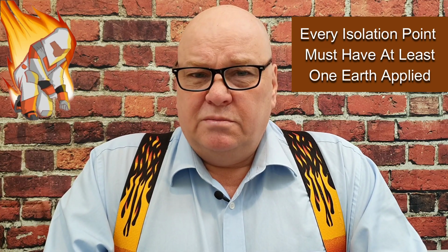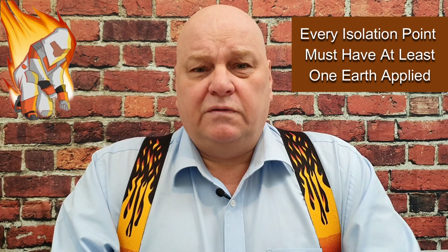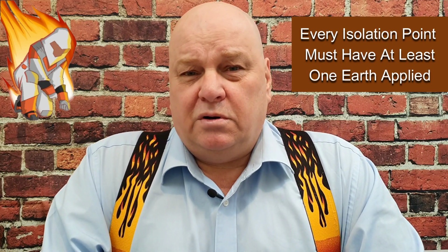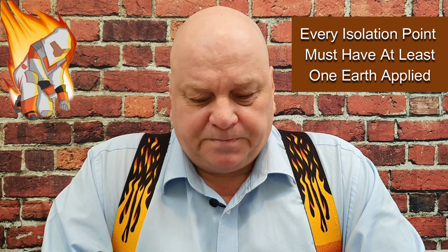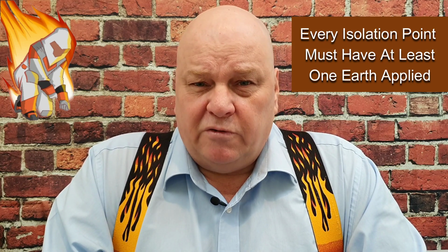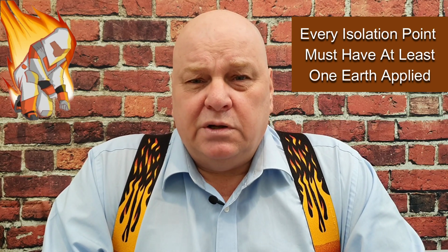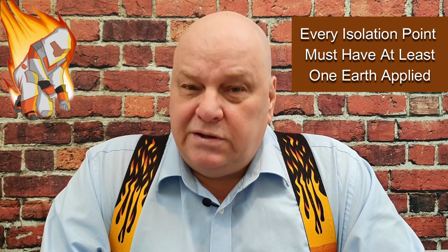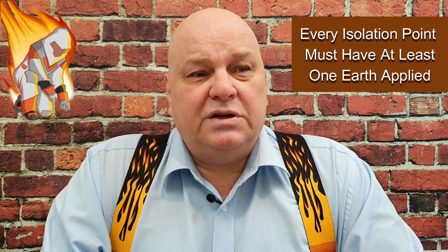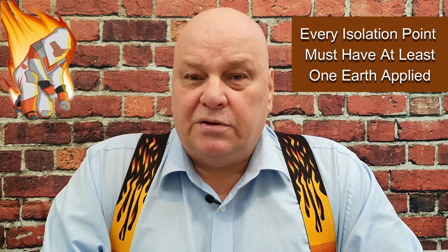But my story in that edition is about the issue of installing PEDs. Installing an insufficient number of PEDs. At every isolation point in HV, we must install at least one earth. And why it says at least is because if we're putting up PEDs, we need to determine how many PEDs are going to be able to do the job.